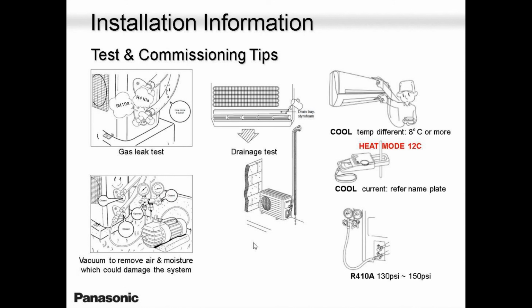When you're vacuuming, you will run away with some of your nitrogen and some of your R410. When you release all the nitrogen and you start vacuuming, whatever was there will go away. And now the system, instead of having 3 pounds, is going to have 2-point-something pounds. The system will run well. Maybe in summertime, no problem. But when it comes to winter, especially when it gets very, very cold, you will have issues. You will have freezing issues. You will have a defrost cycle that will not complete successfully.